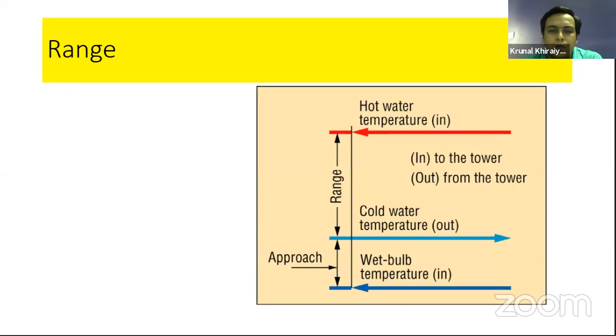Now we are going in depth into the different performance parameters. For understanding of the range, I have kept one figure over here. Hot water, which comes from any heat load, is shown by the red line. The light blue line is the cold water temperature, which comes out from the cooling tower. It means this much temperature is decreased in the cooling tower. And the last one, the very dark blue line, shows the wet bulb temperature of the air, which comes from the atmosphere.